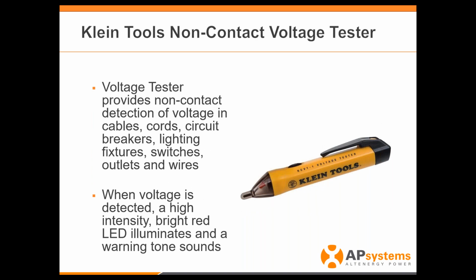Non-contact voltage sensor. This is super great for if you're trying to chase lines that are dead. We had many cases where customers called and said the system's not working, and I said, well, why don't you check the breakers? Because sometimes we see dead breakers or a line that's dead.